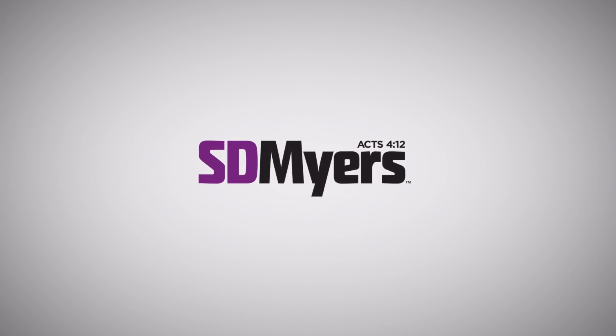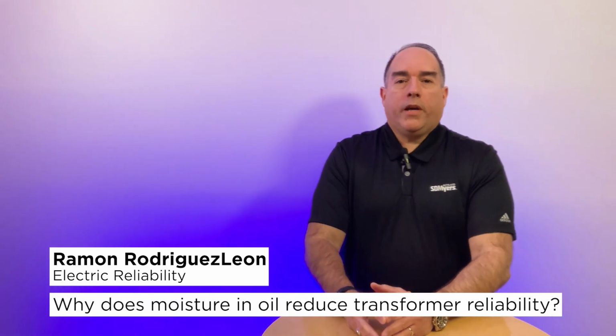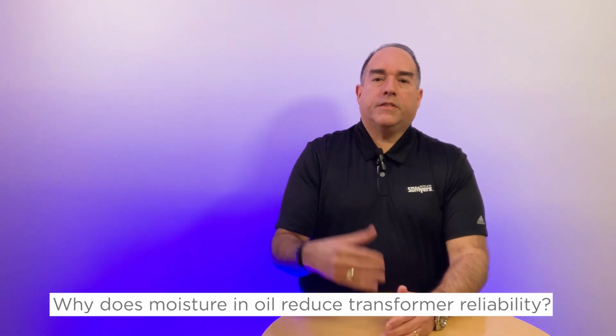Ramon, why does moisture in oil reduce transformer reliability? Sure. Moisture is one of the main enemies of transformers. First, it negatively affects the dielectric properties of the oil in a transformer, and second, it can cause irreversible damage to the paper insulation. As it accelerates the oxidation process, both things can end up leading to a decrease in the reliable life of the transformer.